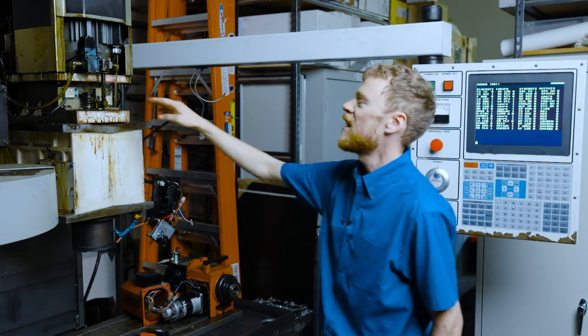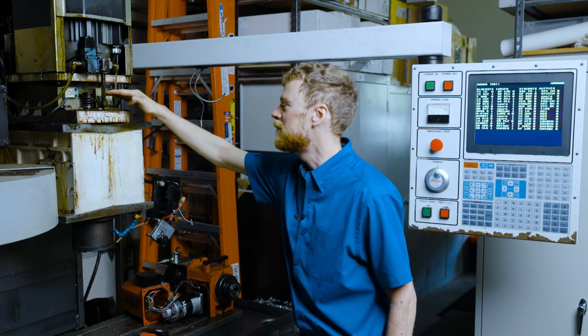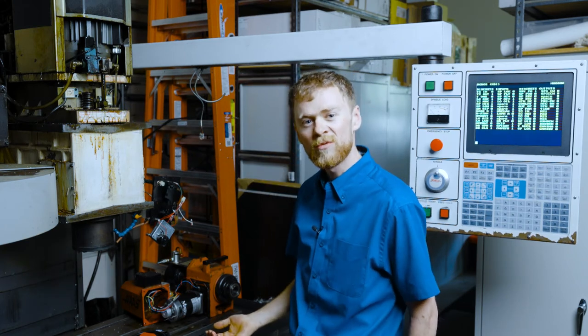At the machine, I saw the quick exhaust valve open up, the pre-charge activate, then it completely unclamped the drawbar. That's the way it should work.